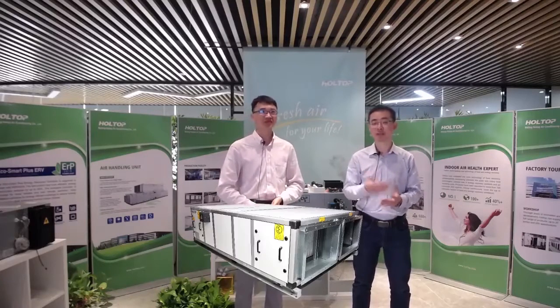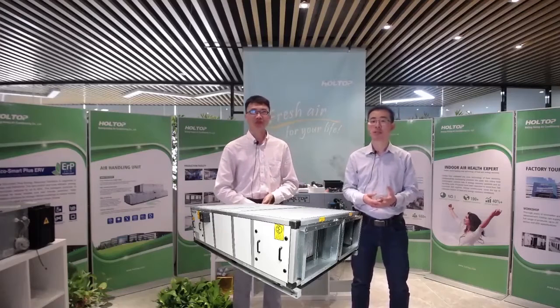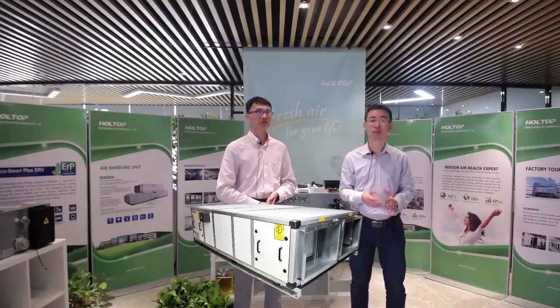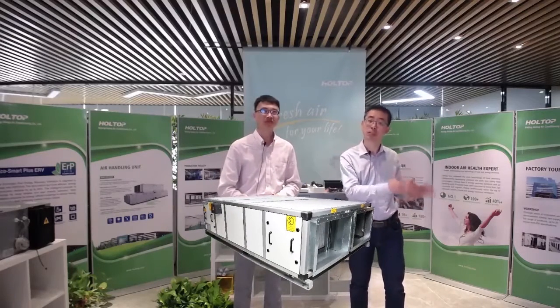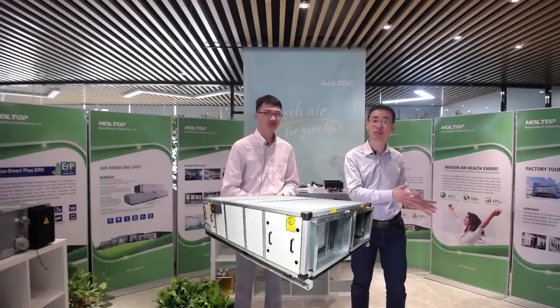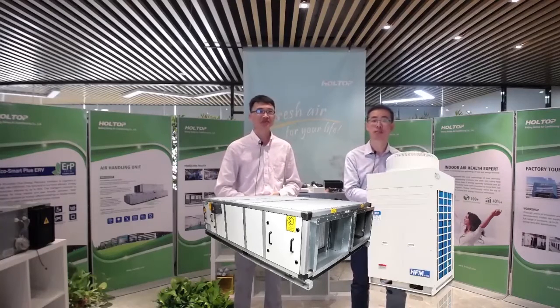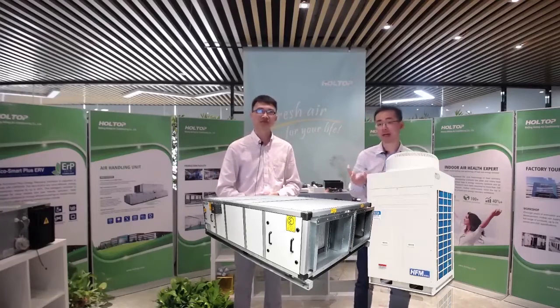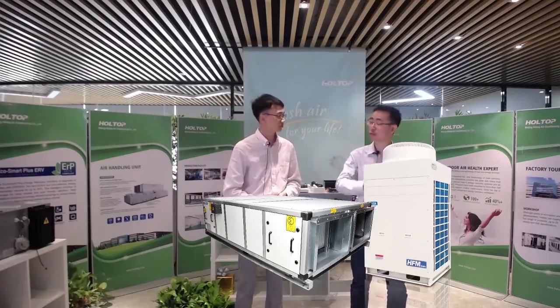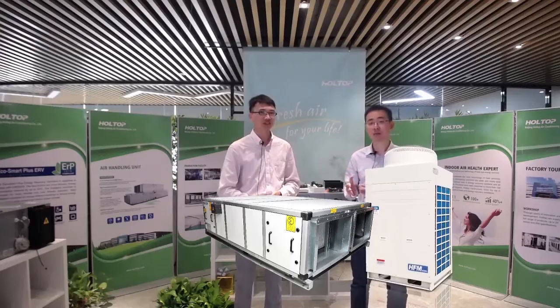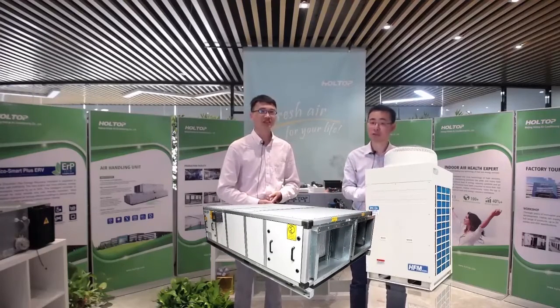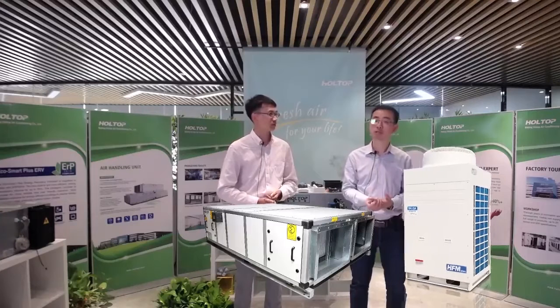The ceiling type DX coil system. This is the split type, which consists of an indoor unit and an outdoor unit, an air-cooled outdoor unit. And actually we have two parts. One is for indoor circulation, and the other one is 100% fresh air. Yeah. And the first one I'm going to introduce is the indoor circulation type. Yeah.